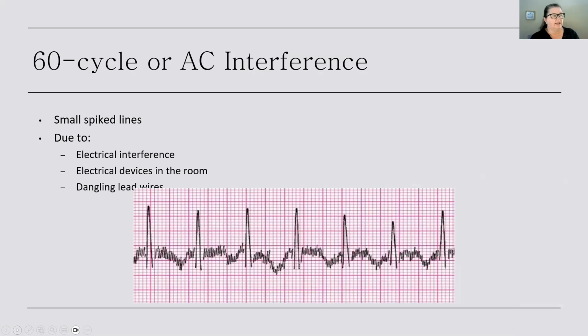60 cycle, or what they call AC interference. I apologize that these got up on here. They look like little spiky lines. I always say they look like electricity to me, which I don't know what electricity looks like, but maybe like a lightning bolt or something. This is usually due to electrical interference. So there's some type of electrical device maybe in the room, their cell phone on them, something like that, that is causing interference electrically with the machine. It also can be due to dangling lead wires. If the lead wires are falling, especially the limb lead wires, because they're longer, if they're dangling off the side of the table, sometimes that can cause this as well. So you just want to check all of that.